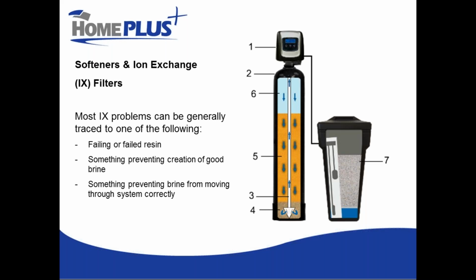So if that little check ball gets stuck in the closed position because of debris, it will prevent us from drawing brine properly. And that's more likely to occur as our brine tank gets dirty. Most modern water softening salts, especially the pellet style, are quite clean. They don't contain a lot of impurities, but there are still some impurities that don't dissolve and they will accumulate in the bottom of our brine tank.